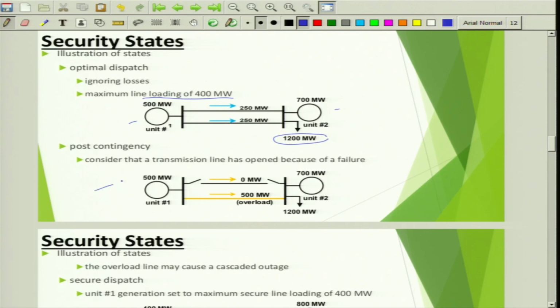Whereas in the post contingency you can see, consider that a transmission line has opened because of a failure. If this first line is gone, what is happening now? 500 has to flow through only one line, but there is an overload.